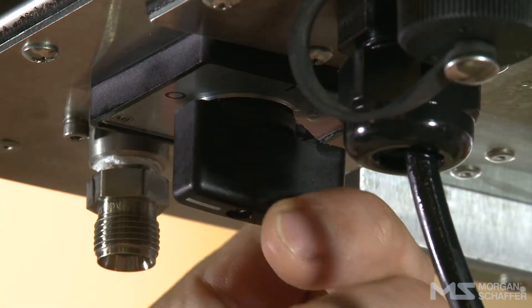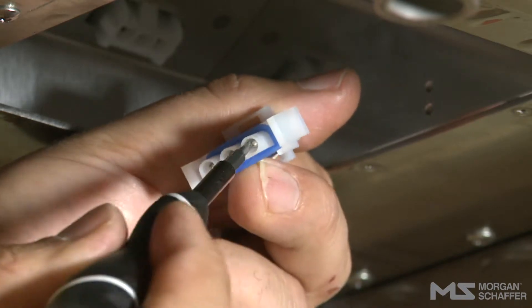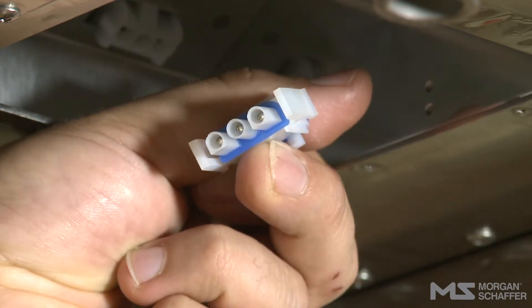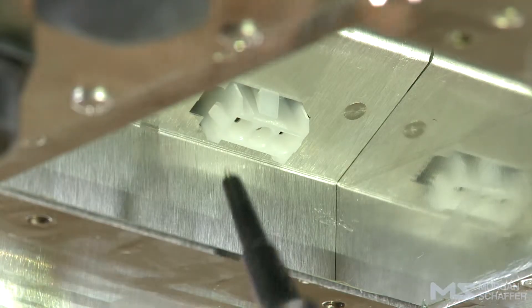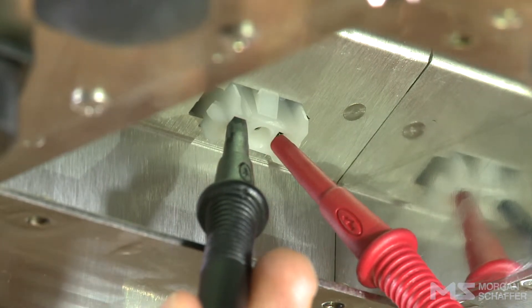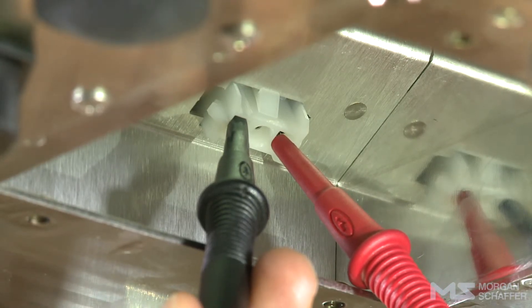Turn off the Callisto. Check that the connector's male and female pins are in good contact and that the connectors are clean and in good condition. If not, clean and/or repair them. Check the fan's external power supply. Unplug the fan and, using a multimeter, check that there are 13.5 volts DC between pins 1 and 3 of the Callisto's female connector. If there are not between 13 and 13.5 volts DC between pins 1 and 3, please contact Morgan Schaffer.